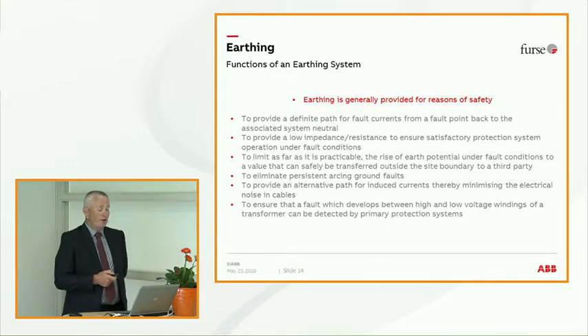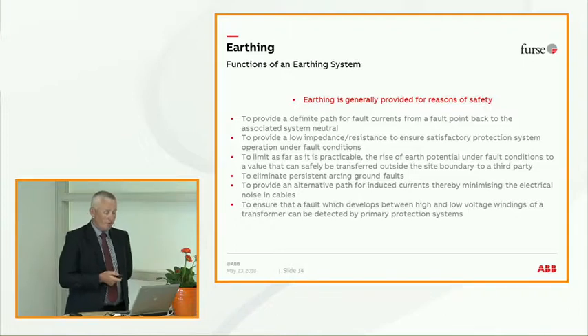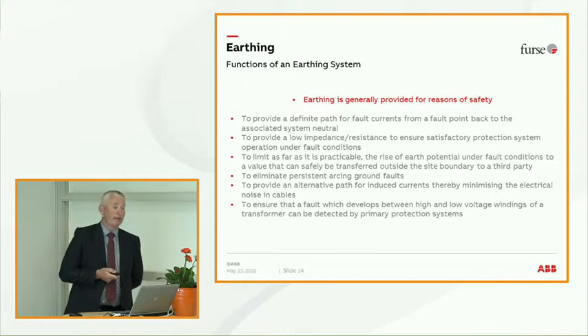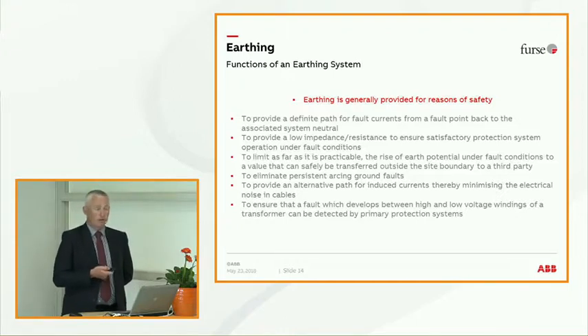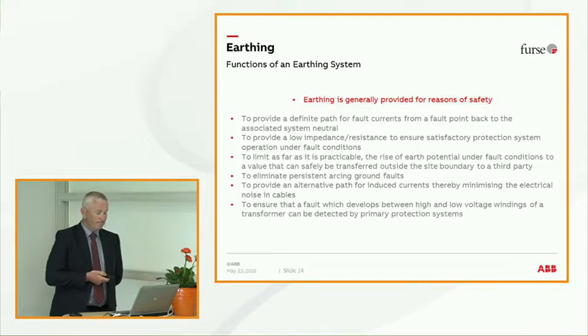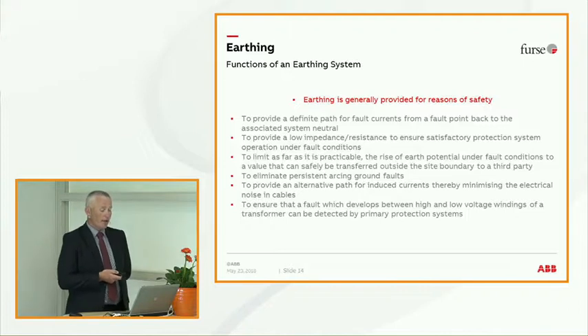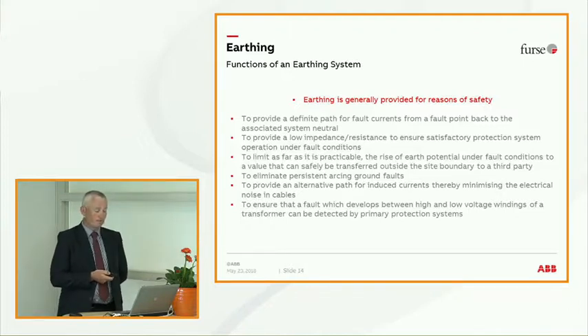The function of an earthing system is to provide the path to earth through a system neutral. It's to provide that low impedance, the least resistance to earth, and to limit, as far as practical, the rise of potential. I will mention that a little bit later, but the potential is the dangerous effect of the electric currents that can kill. It's to eliminate persistent arcing. This is again dangerous, can cause fires and cause damage. And it's to ensure that a fault which develops between high and low voltage windings can be detected by the protection system.